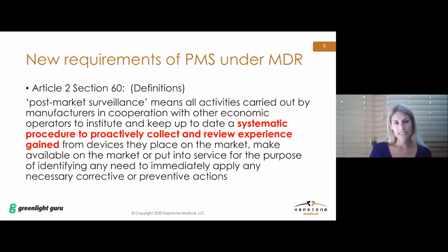All right, I think it's important to understand how post-market surveillance has been defined in the EU MDR, as this drives the further requirements. So in Article 2, Section 60, post-market surveillance is defined as all activities carried out by manufacturers in cooperation with other economic operators. And I know that economic operators were discussed in an earlier webinar, so hopefully you attended that. So in cooperation with other economic operators to institute and keep up to date, this is the important part, a systematic procedure to proactively collect and review experience gained from devices they place on the market. So as highlighted in red, that's the crux of the definition: systematic and proactively.